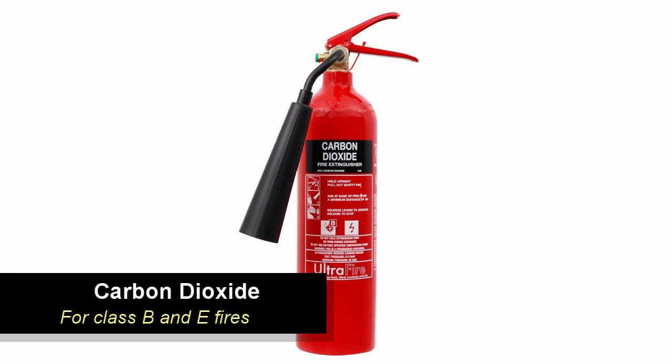Carbon dioxide extinguishers work by driving out the oxygen, smothering the fire. Particularly suitable for fires involving electrical equipment, as they will extinguish a fire without causing any further damage, except in the case of some electronic equipment, for example computers. As with all fires involving electrical equipment, the power should be disconnected if possible.